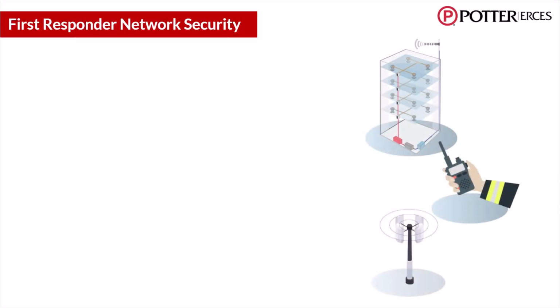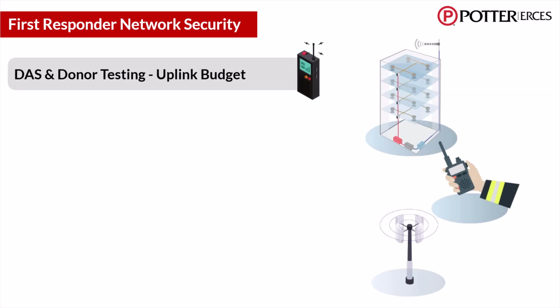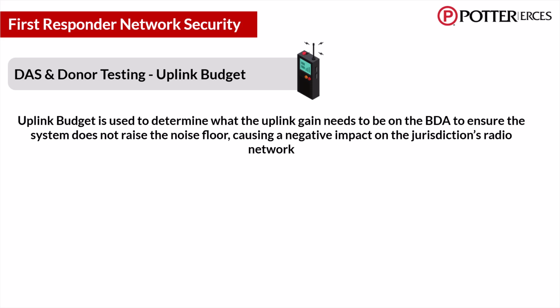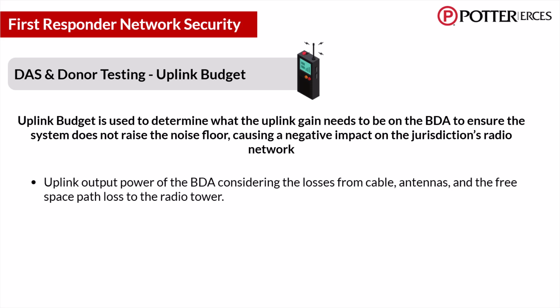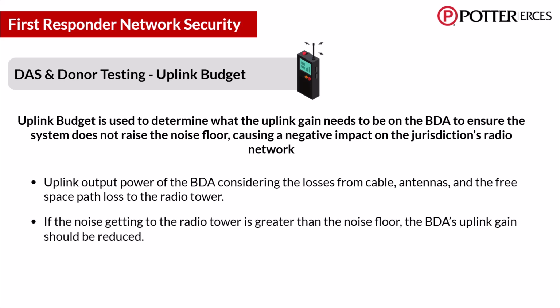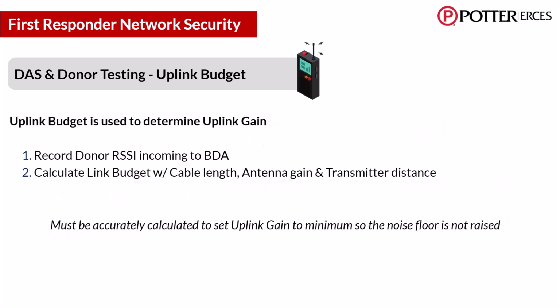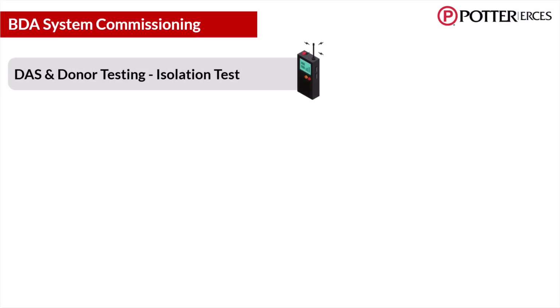One of the most important parts of protecting the local radio network is creating and understanding the uplink budget. The uplink budget is used to determine what the uplink gain needs to be on the BDA to ensure the system does not raise the noise floor, causing a negative impact on the jurisdiction's radio network. The uplink budget is determined by calculating the uplink output power of the BDA and considering the losses from cable, antennas, and the free space path loss to the radio tower. If the noise getting to the radio tower is greater than the noise floor, the BDA's uplink gain should be reduced. Another important test to conduct is called an isolation test.